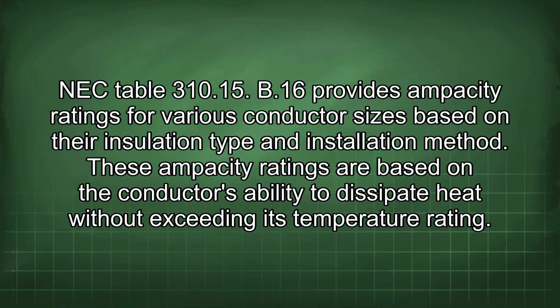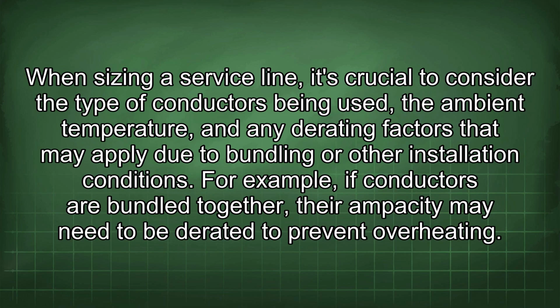NEC Table 310.15(B)(16) provides ampacity ratings for various conductor sizes based on their insulation type and installation method. These ampacity ratings are based on the conductor's ability to dissipate heat without exceeding its temperature rating. When sizing a service line, it's crucial to consider the type of conductors being used, the ambient temperature, and any derating factors that may apply due to bundling or other installation conditions. For example, if conductors are bundled together, their ampacity may need to be derated to prevent overheating.